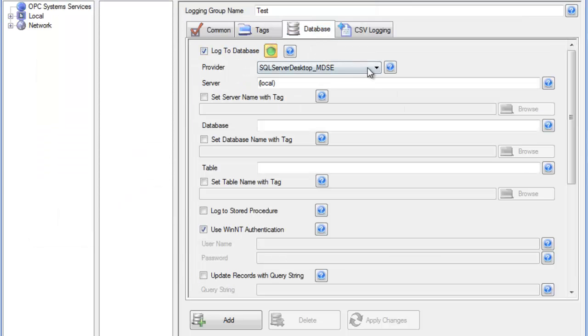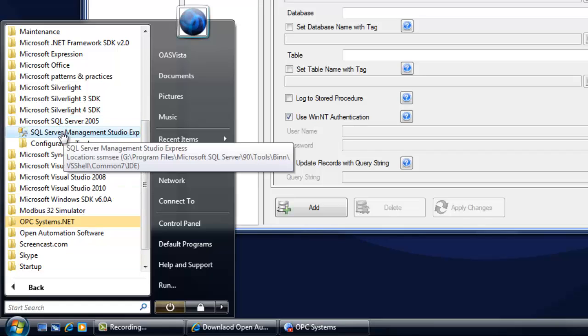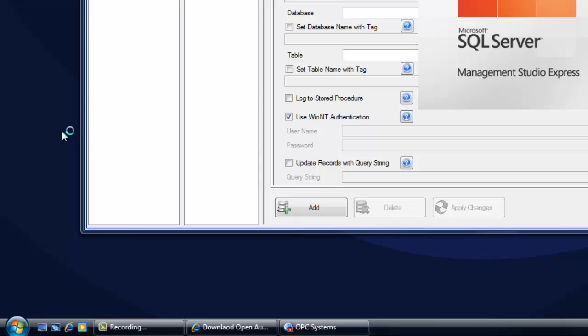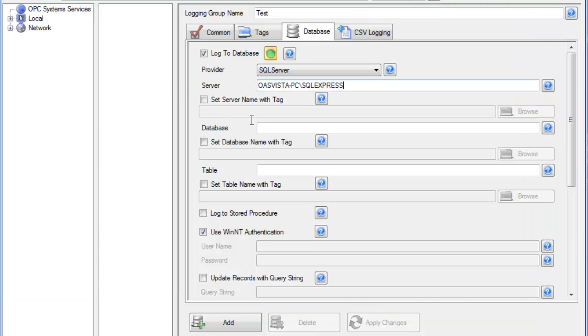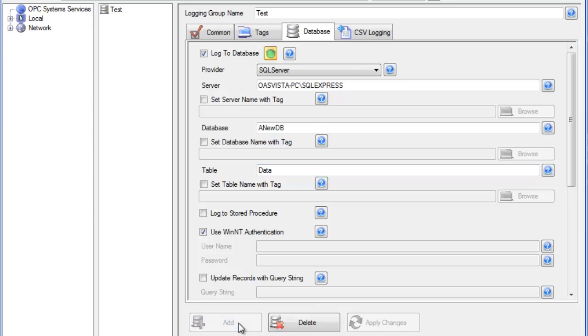Under the Database tab, specify where to log the values. Choosing SQL Server as the database engine, use Microsoft SQL Server Management Studio to find the server name. We can also log to remote database engines — just as reliable because of the data buffering feature. Enter a database name and table name. Once added to the configuration, the service creates the database and table with the defined field names and begins logging at a one-second frequency into the database engine.